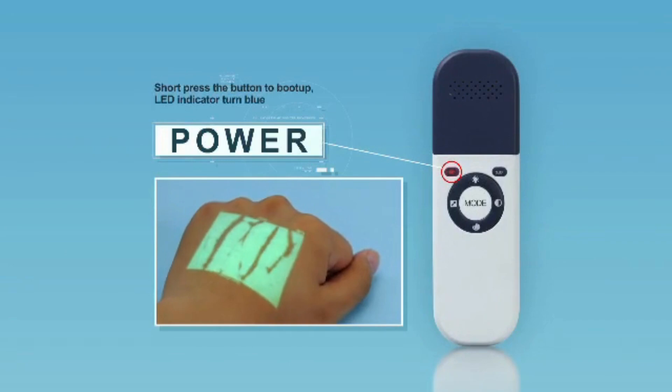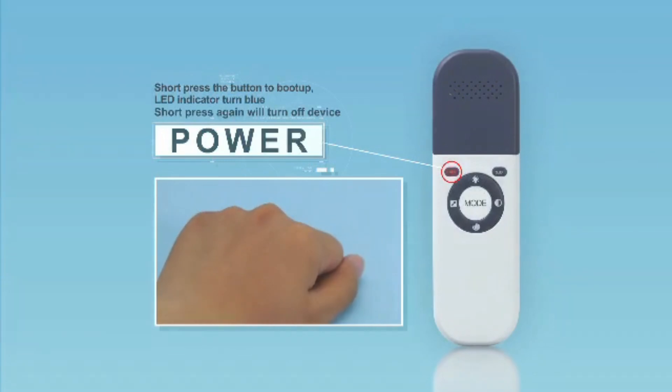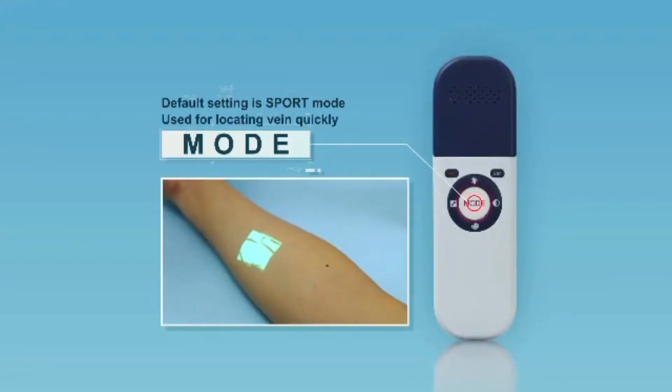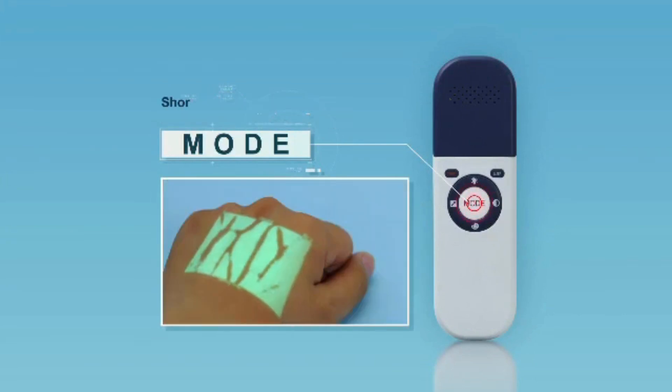To power on VeinFinder, short press the power button. Short press again to turn the device off. Two display modes include sport and enhance. Default setting is sport mode for locating veins quickly. Short press mode button to switch to enhance mode, which is used for viewing finer image details of smaller and deeper veins, especially for pediatrics, obese patients, and edema patients.